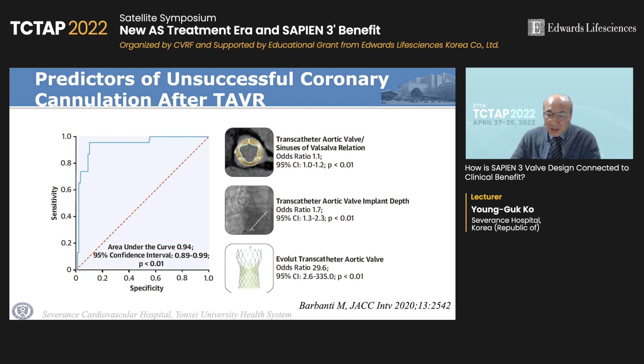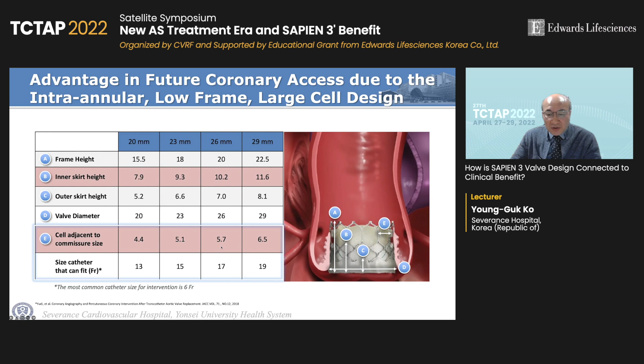And SAPIEN 3 shows an advantage in future coronary access due to its intra-annular, low frame and large cell design. The inner skirt height ranges between 7.9 and 11.6 millimeters according to valve size. And the size of the cells adjacent to the commissure varies from 4.4 to 6.5 millimeters, which is sufficient to accommodate the guiding catheters.